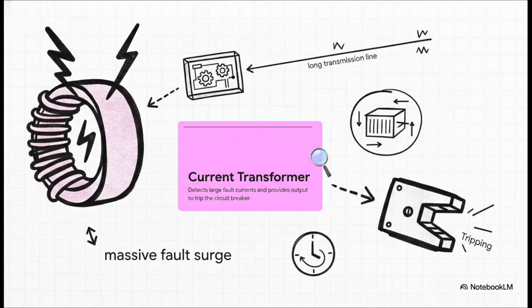But here's the thing, a circuit breaker is blind. It relies on a current transformer, or CT, to detect the massive fault surge and signal a protective relay to trip. And there are three main relay schemes that cover the overwhelming majority of protection applications. First, overcurrent relays. These are the simplest. They trip when current exceeds a set threshold, using a time delay curve that trips faster as current gets higher.